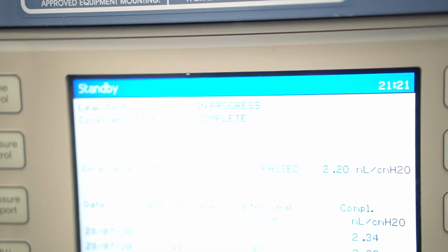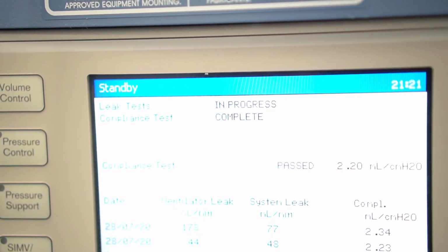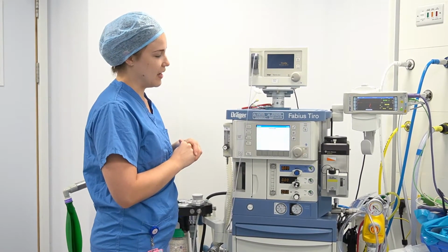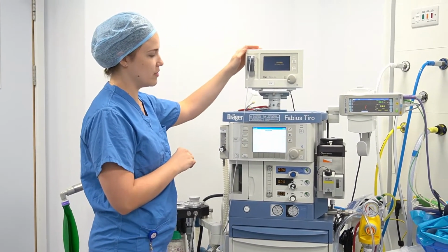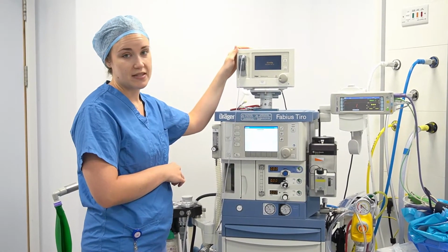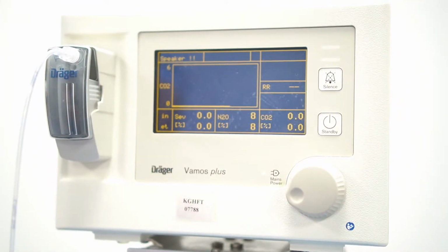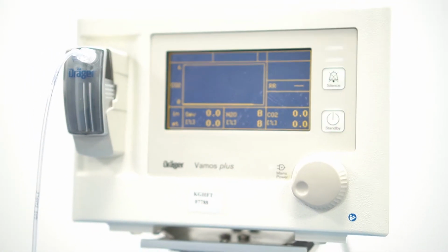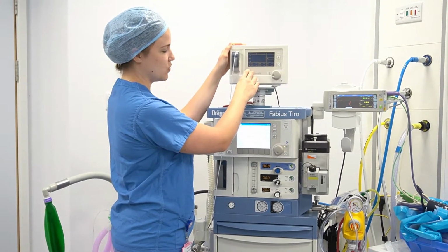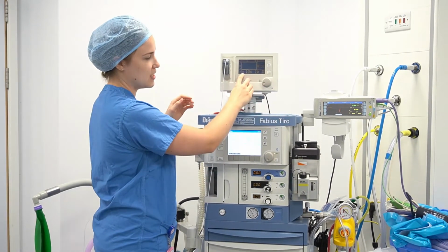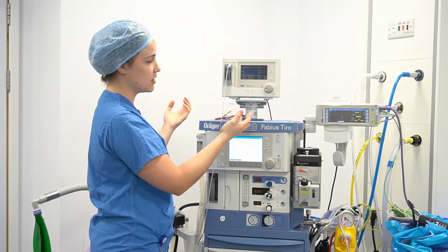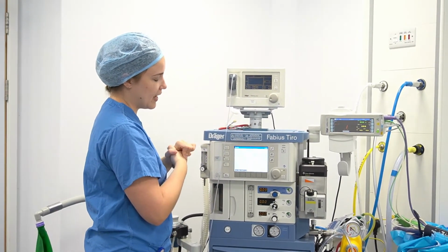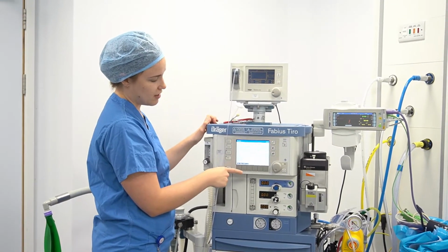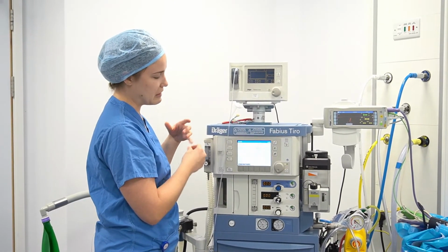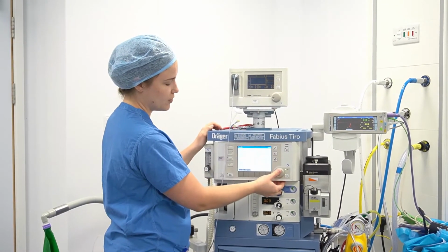So it's now just completing the test itself, which sounds like it's nearly done. And then we're just going to take a look at this screen over here. This is your gas monitoring. If you turn this on over here, it's going to be monitoring your input and your end tidal of your sevoflurane, of your nitrous if you're using it, and then your carbon dioxide. As we can see over here, the machine has said that it's passed both the leak and the compliance test, and again press the rotary knob to exit.